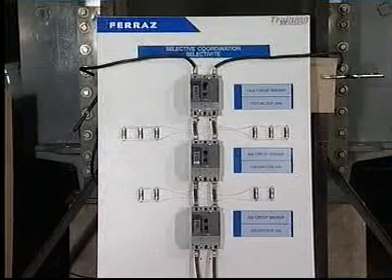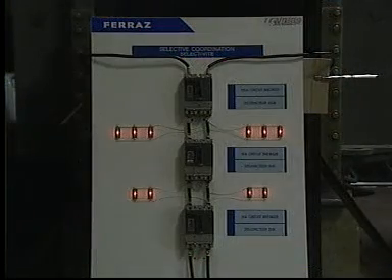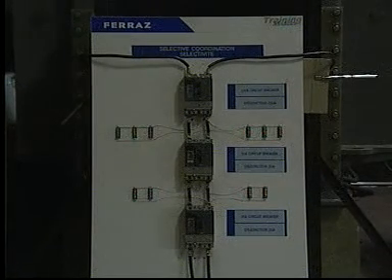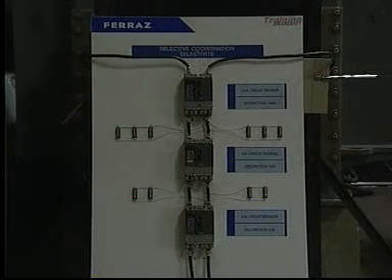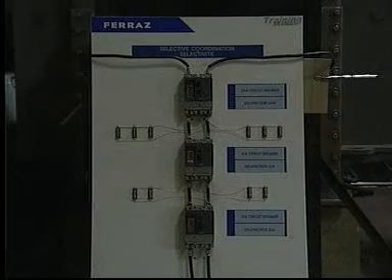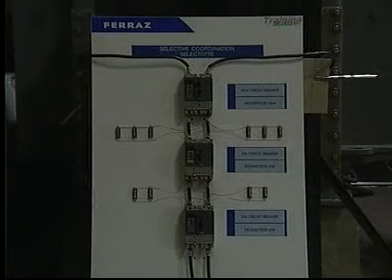The third test is the same as test 2, except that the fault current has been increased to 25,000 amperes. The result is that all three breakers open, thereby causing a total system blackout. This could be predicted, since the fault current is above 20,000 amperes where there is no short time trip delay.